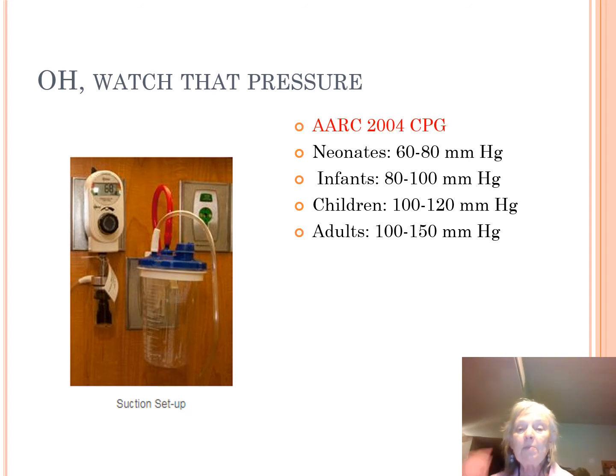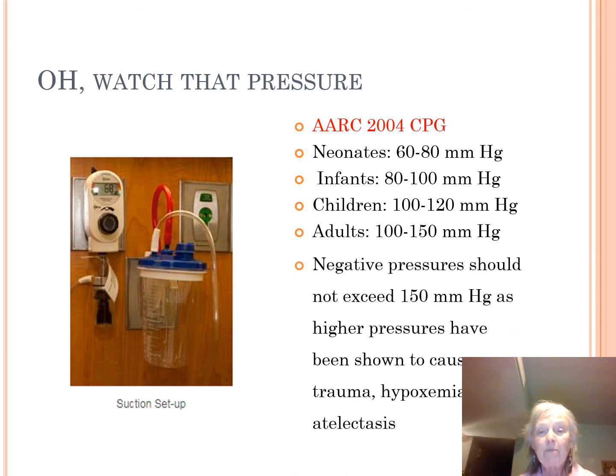Now, sometimes when you're looking in the literature, people will say, well, the children's high is 120, so therefore the adults' low level should begin at 120. That is not what the guidelines say. So when you see the suction pressure you're going to use, it's -100 to -150. And there you see negative pressure should not exceed 150 millimeters of mercury, as the higher pressures have been known to cause trauma, hypoxemia, atelectasis.